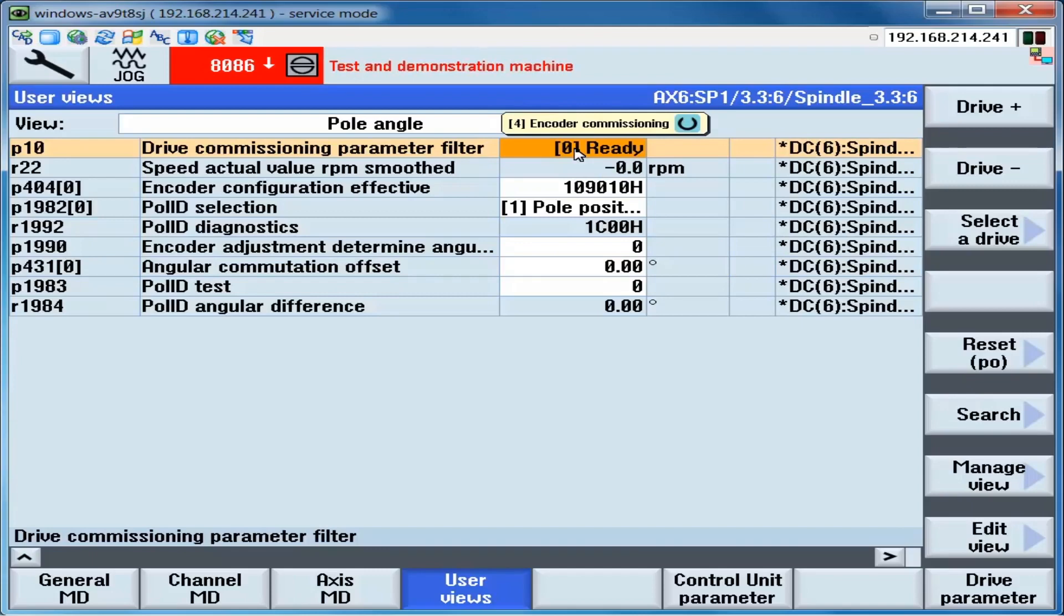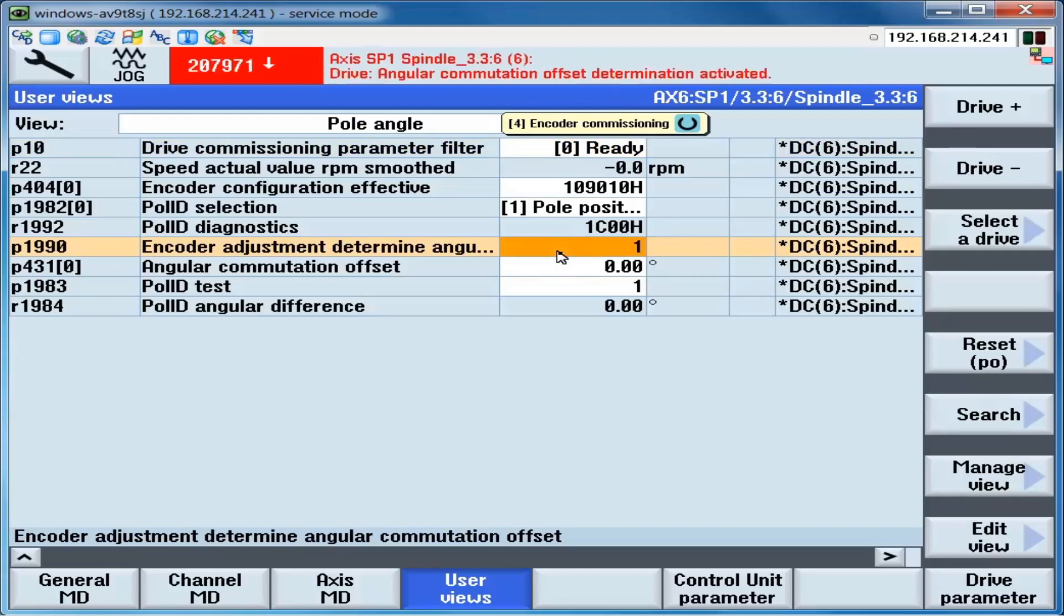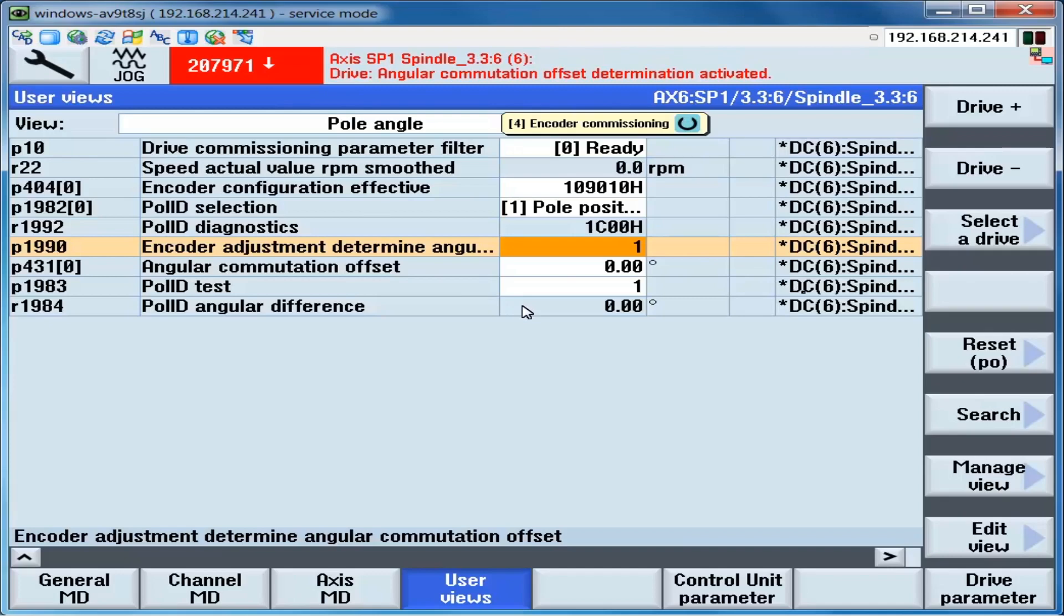The drive must be in the disabled state. The parameter P1990 is set to a 1. The message 207971 Drive Angular Commutation Offset Determination Activated appears. Then the drive must be enabled. When the drive is enabled, the coarse commutation angle will be determined by the drive. Enable the drive.